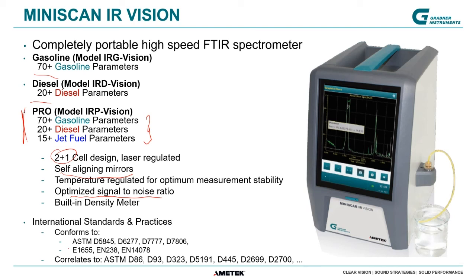There are international standards and practices supported — for oxygenates, benzene, density, biodiesel, and corresponding EN standards — as well as a wide range of standards to which we correlate. Correlation means predicting the properties I mentioned. To create the database for property prediction, you take results from original reference standards — such as the RON engine method — and feed that information along with the spectrum into the instrument. As long as the fuel composition has a relationship with the property, you can find features in the spectrum to correlate, and this database of fuels and number of parameters is constantly growing.